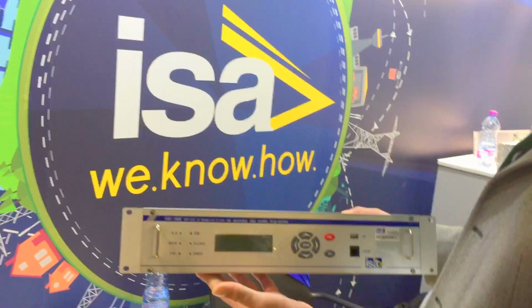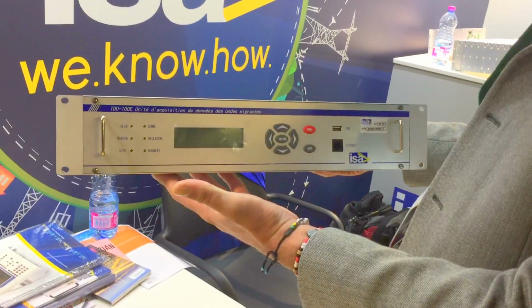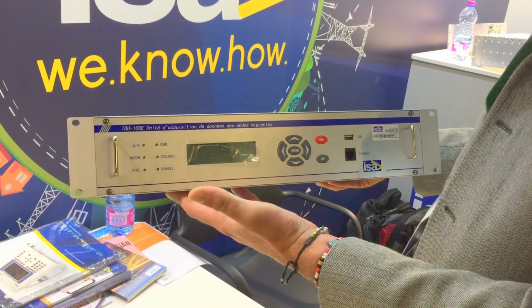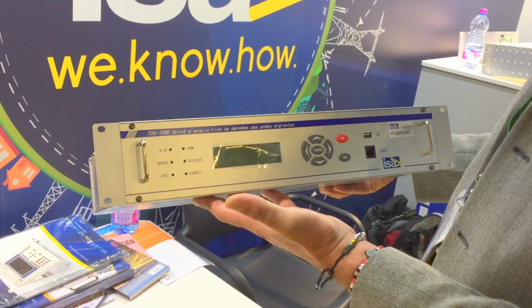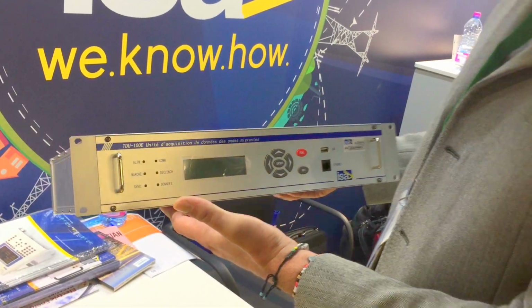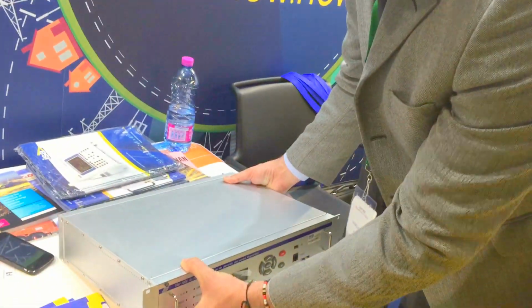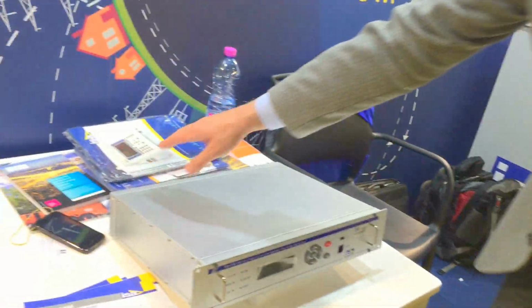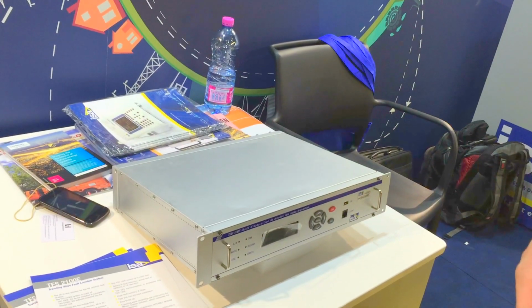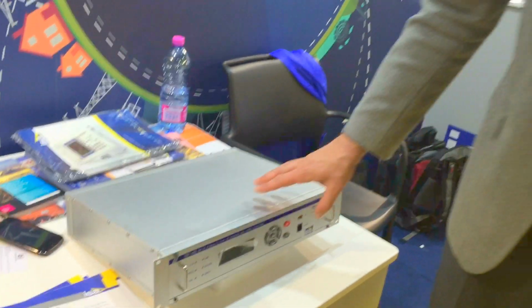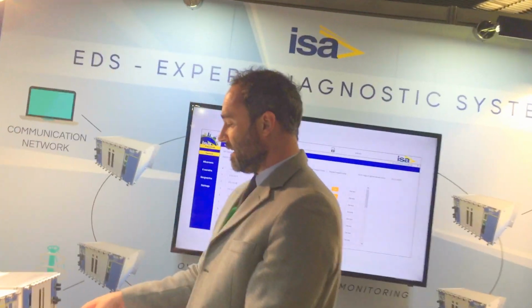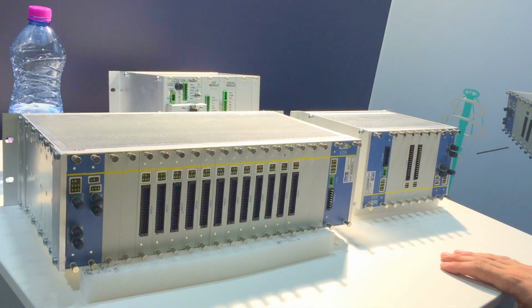TFS is a fault locator, so using travel waves with a high accuracy of up to 50 meters. As mentioned, travel waves are used here and the installation is very non-intrusive. You just need to connect the clip-on CTs to your protective relays, and thus you configure the TFS. Moving on, the new product is EDS.